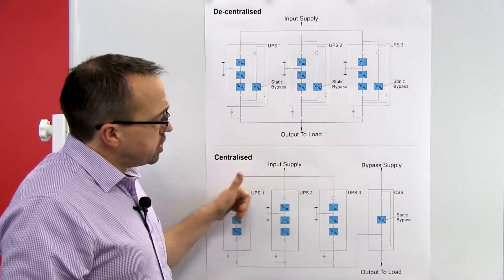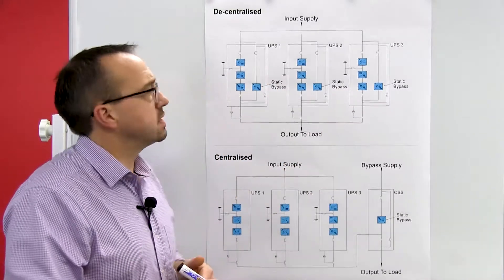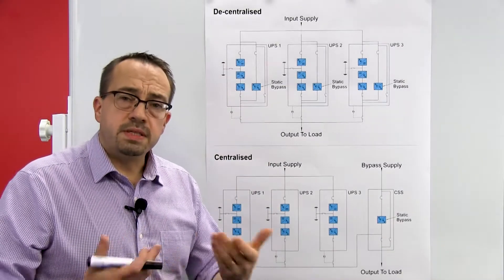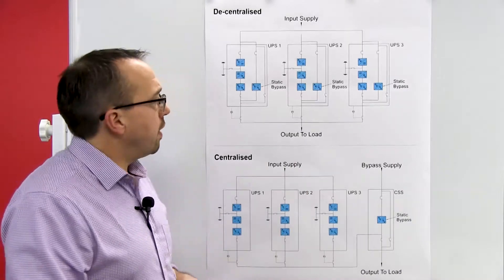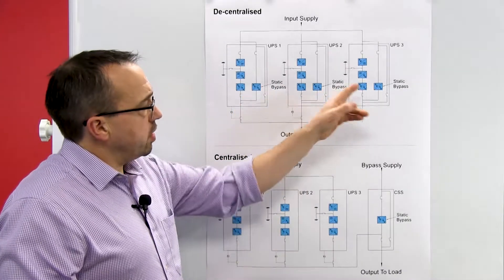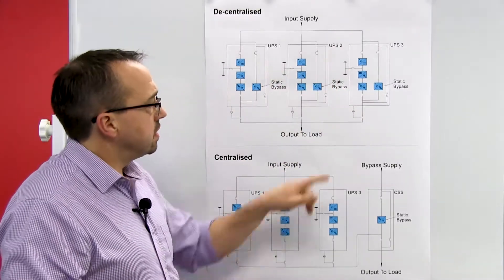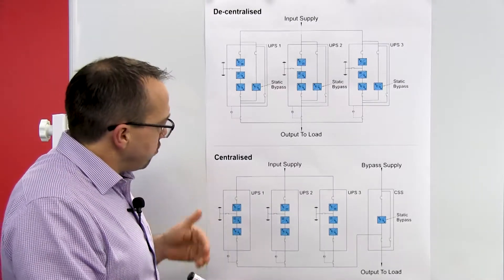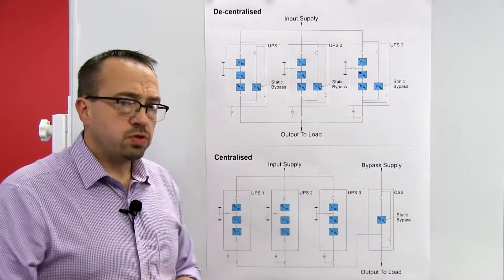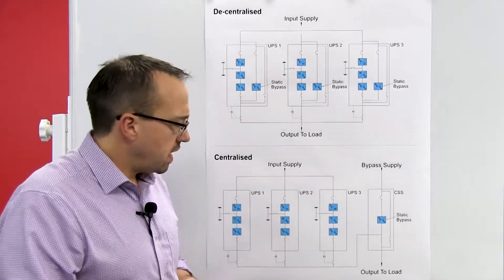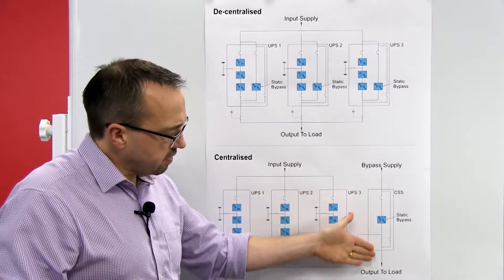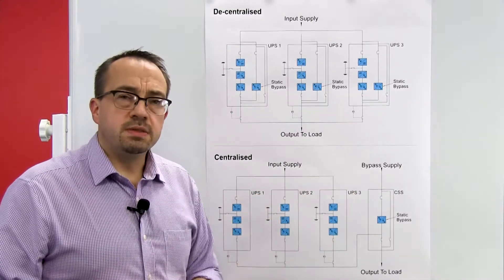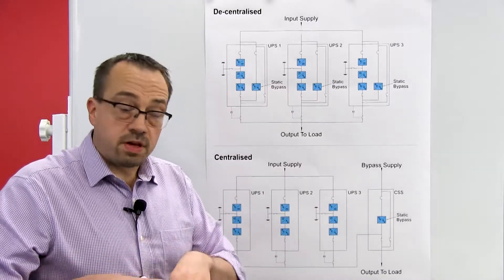In addition to operational resilience, you must consider maintenance resilience. In the decentralized system, if you need to maintain a UPS you simply power it down, carry out maintenance, and power it back on — the remaining operational modules still support the critical load and provide static bypass availability at all times. With the centralized system you can maintain the UPS modules without issue, however when you need to maintain the static bypass module you are removing bypass availability from the entire UPS system, reducing the resilience level during that maintenance period.